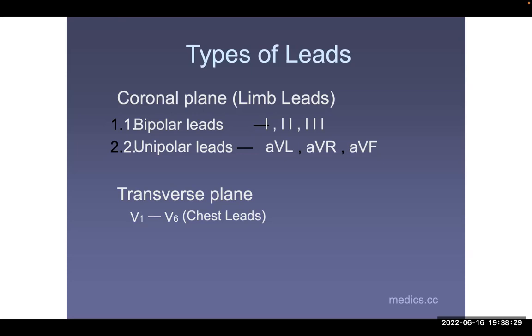aVL is usually on the left upper limb, aVR on the right upper limb, and aVF on the left foot. When connecting patients to the 12-lead ECG, leads are color-coded: red is on the right arm, yellow on the left arm, green on the left foot, and black — which is neutral — on the right foot. I encourage all of you to go to the ward, get an ECG tracing, and look at the color coding and what they mean, and where V1, V2, V3 are placed.